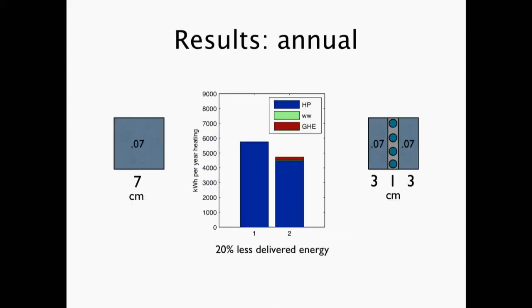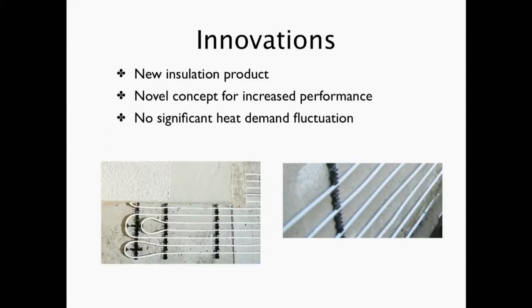This was an example of that kind of system, where again we had 20% less energy for the same thickness wall—7 centimeters and 7 centimeters, the exact same—including all the pumping costs for putting water into this piping system. So in the end, we have this new product, a novel concept with increased performance, and it doesn't have any significant fluctuation in heat demand over the year, which makes the engineers happy.